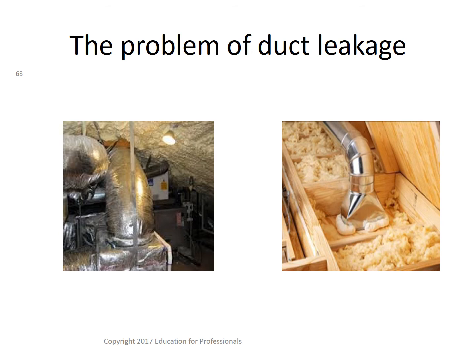And just to say what the problem of duct leakage is: many studies conducted throughout the country have found that poorly sealed ductwork is often the most prevalent and yet easily solved problem in new construction. Duct leakage does contribute to 10 to 30% of heating and cooling loads in many homes. That would be through the loss of air through poorly sealed portions of duct and improperly engineered ductwork. Additionally, duct leakage can lessen comfort, which also endangers health and safety.